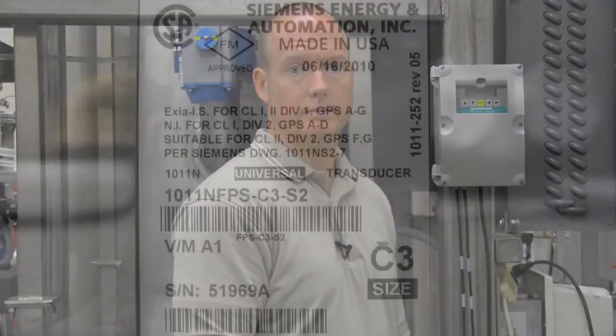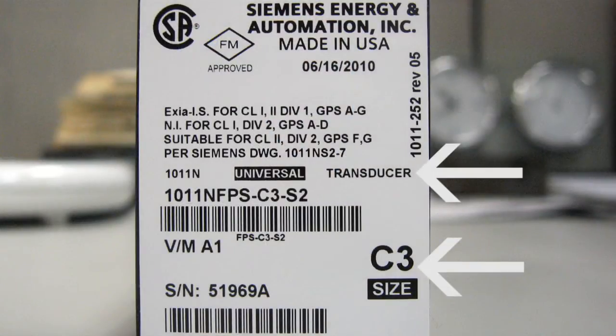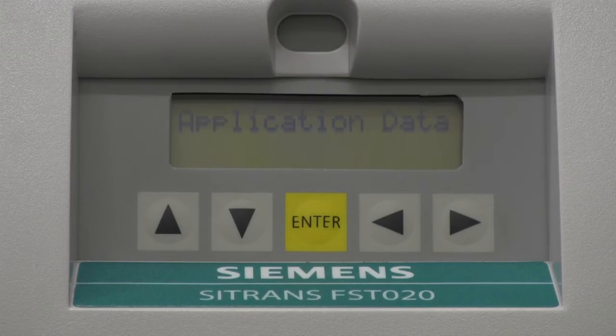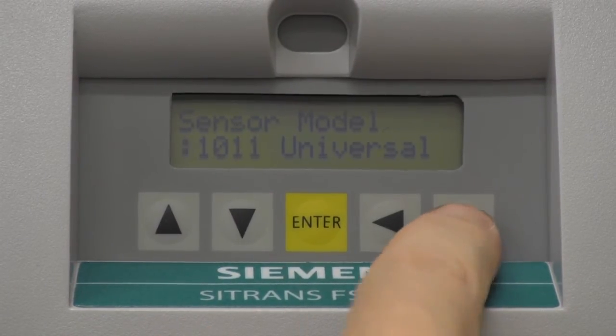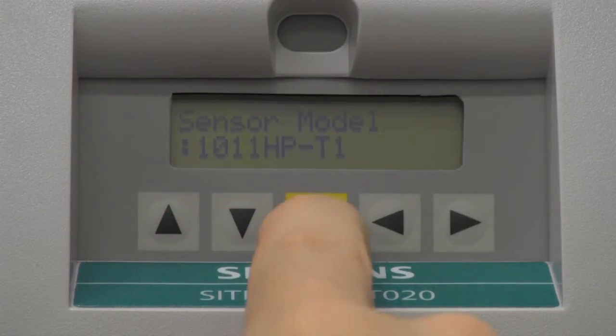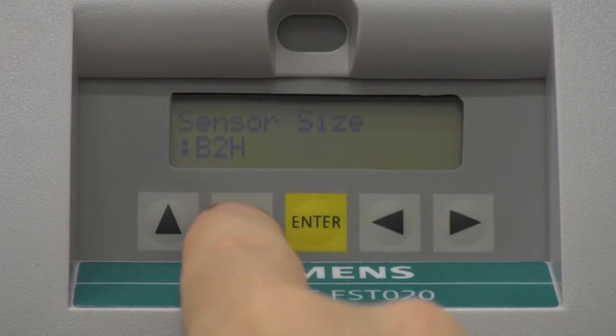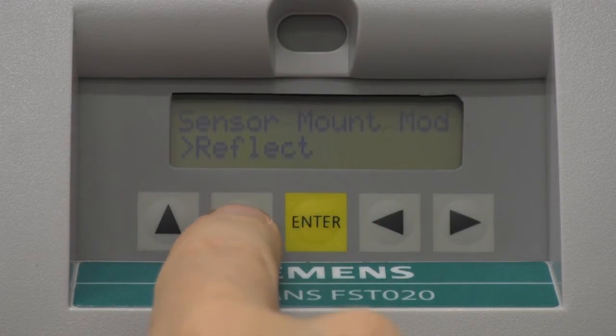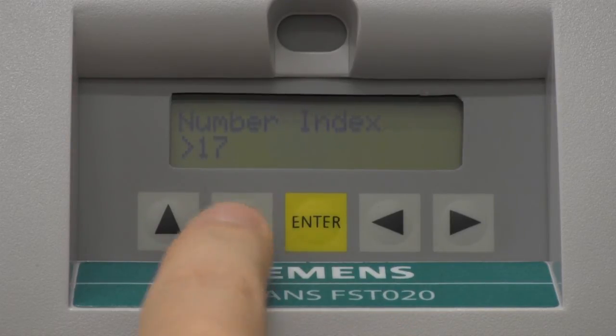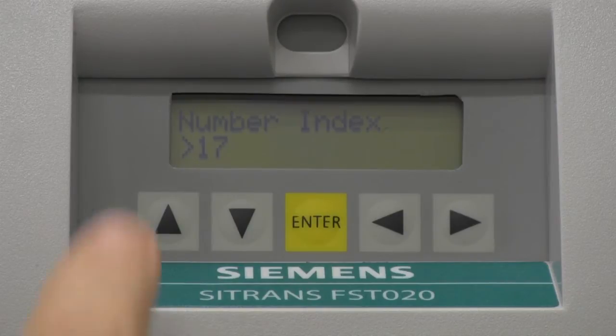Now we will enter the sensor data into the FST020, which will help us mount the sensors for optimal performance. The data we need is the sensor type and size, both of which can be found on the sensor label. Navigate to the Install Sensor screen and from the drop-down menu, select the sensor model and size. The FST020 will recommend the preferred mounting mode — either direct mount or reflect mount — and will also calculate the spacing number index. Please record this index number, as it is used to properly position the sensors along the pipe.